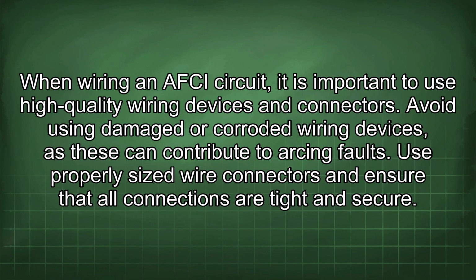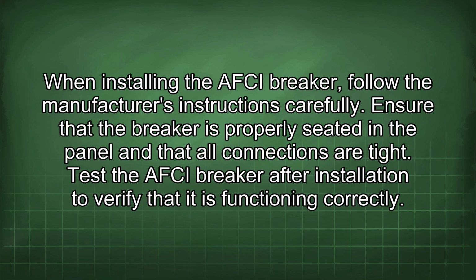When wiring an AFCI circuit, it is important to use high-quality wiring devices and connectors. Avoid using damaged or corroded wiring devices, as these can contribute to arcing faults. Use properly sized wire connectors and ensure that all connections are tight and secure. When installing the AFCI breaker, follow the manufacturer's instructions carefully. Ensure that the breaker is properly seated in the panel and that all connections are tight. Test the AFCI breaker after installation to verify that it is functioning correctly.